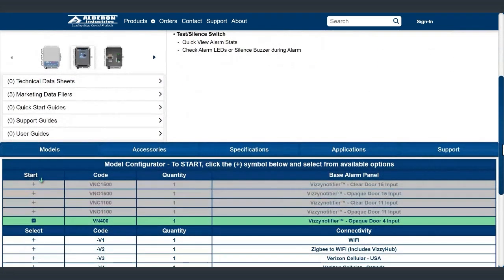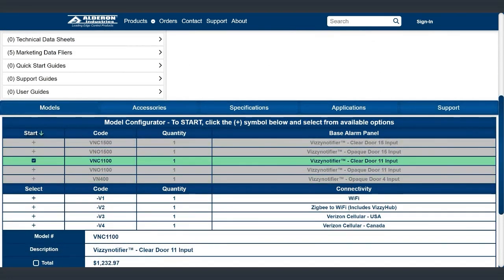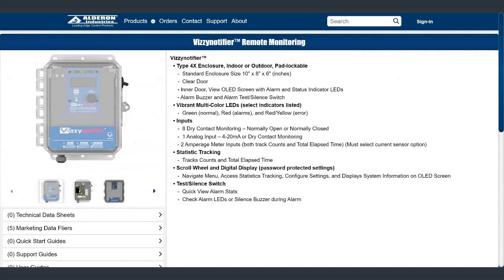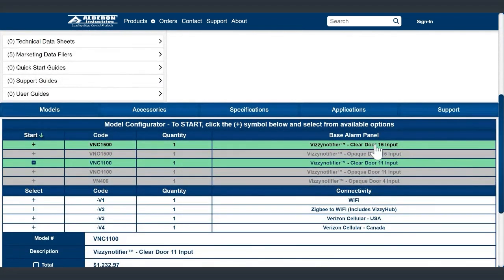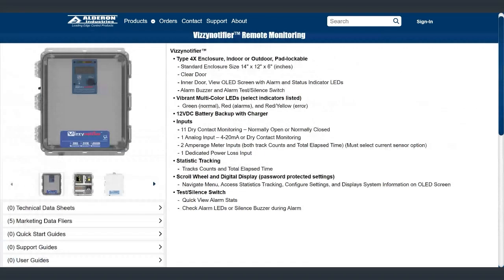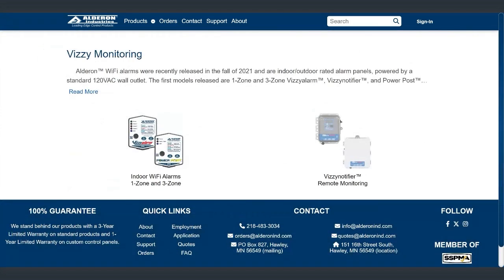And then we have another model that has 11 inputs. And the one with 11 inputs has 8 dry contacts, 1 analog input, which you could use a 4 to 20 milliamp signal on, and then 2 of them you can use for ammeter input. And then we also have a 15 input model. And that one has 11 dry contacts, 1 analog input, 4 to 20 milliamp, 2 ammeter inputs, and 1 dedicated power loss input. And this one you can have battery backup on as well. You can input a 12-volt battery backup in there, motorcycle battery. So some options with that, and with those.